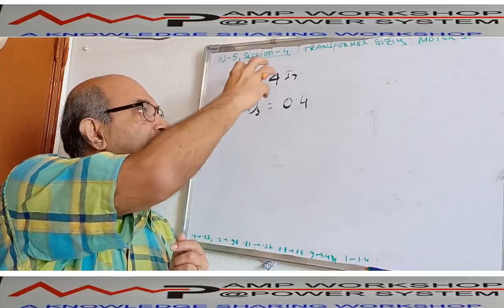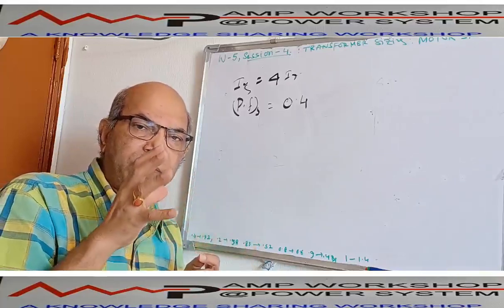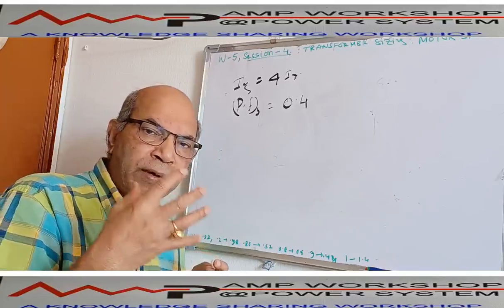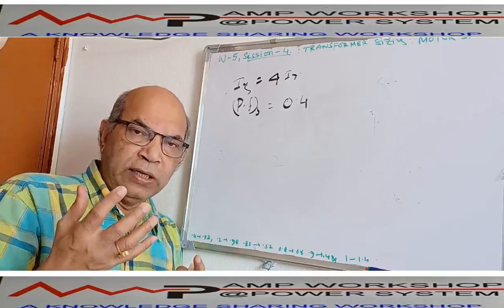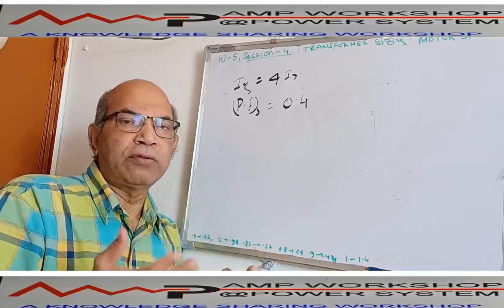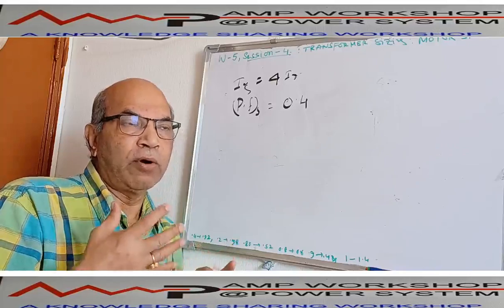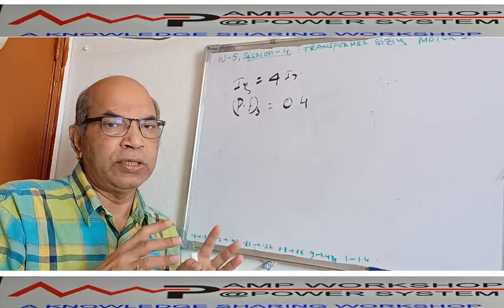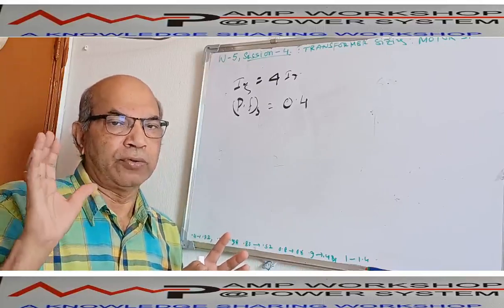Now, in the transformer running condition, when the transformer is catering power to the motor for running, the amount of kVA drawn from the system is different from the amount of power drawn during starting, so automatically the voltage drop will be different. We have to check that during starting, the transformer maintains its terminal voltage to meet the motor starting as well as the system voltage, and during running also it maintains the voltage. So the voltage drop part we also need to check during motor starting and motor running to size the transformer. These are the three main aspects we have to consider during sizing of a transformer dedicated to a single motor.